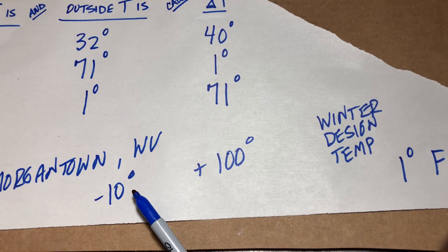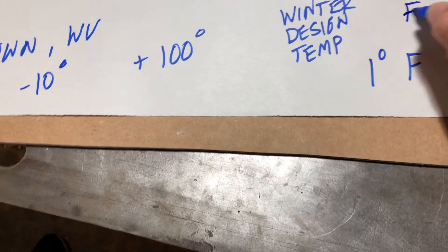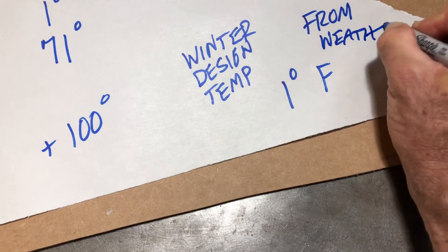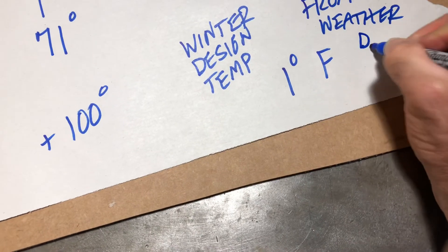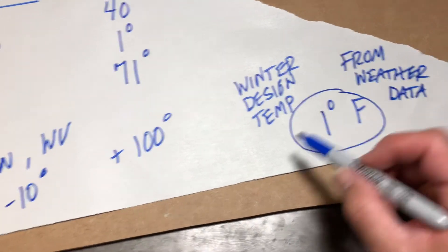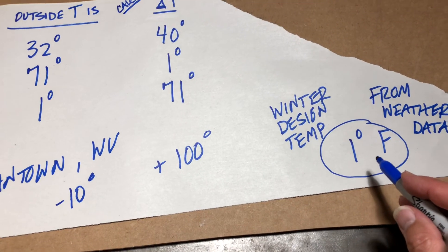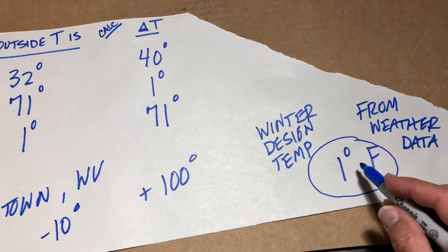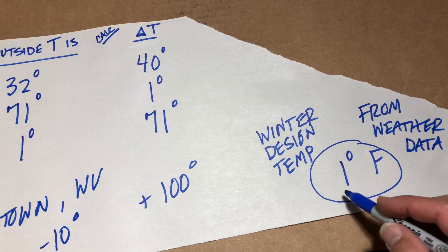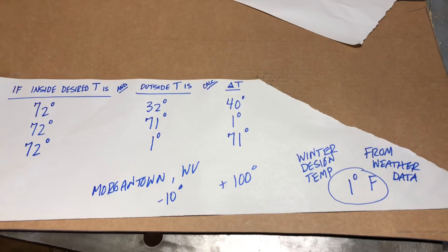So the winter design temperature comes from weather data, and we're going to use 1 degree for Morgantown. It would be very different for Florida — a lot higher — and very different for somewhere way up in Maine — a lot lower. But that's the concept, so get that in your head. You'll be seeing that delta T when we do the design heat load calculations.